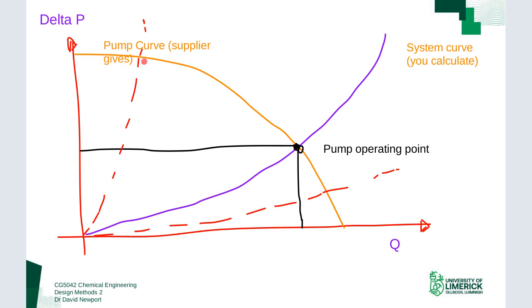We use the pump curve to determine the operating point. The pump curve is a pressure-flow curve that is produced by the supplier — this is something the manufacturer gives you. You plot this curve with your system curve, and where the two intersect gives you your pump operating point. This particular pump has a characteristic curve for a centrifugal pump, which is the workhorse of the process industry. The intersection gives the flow rate and the pressure rise experienced in the system.